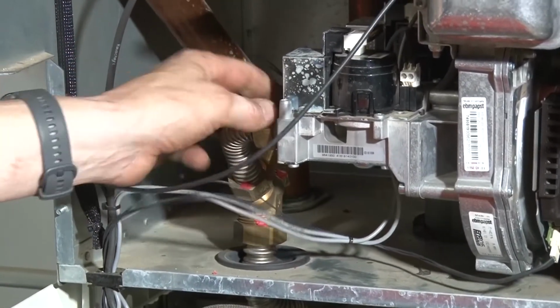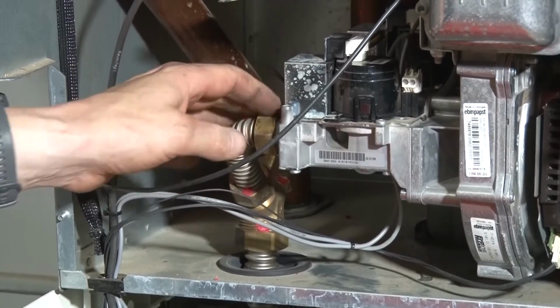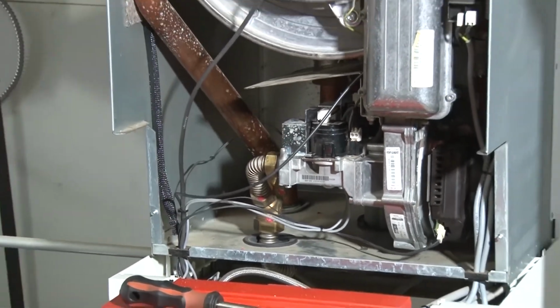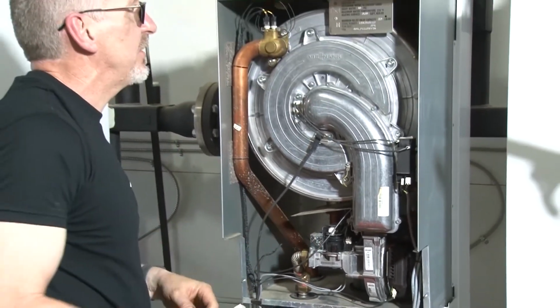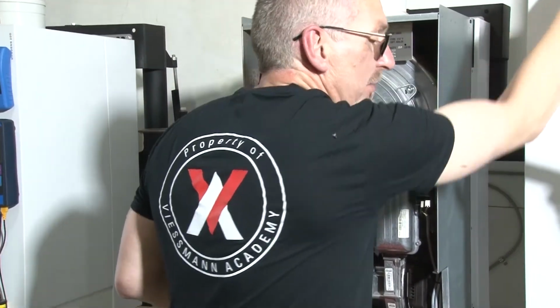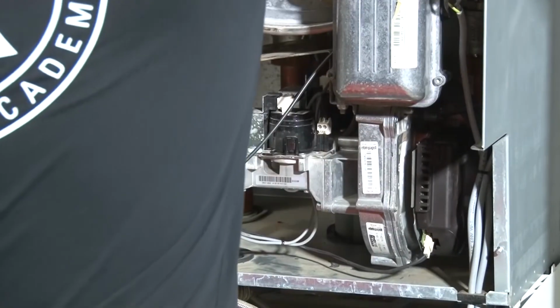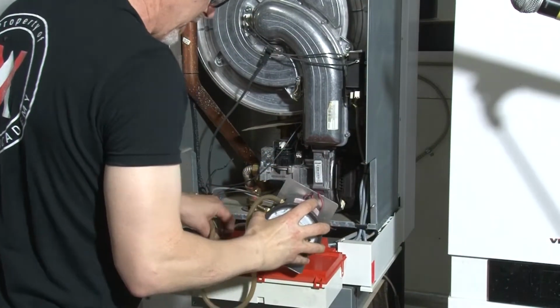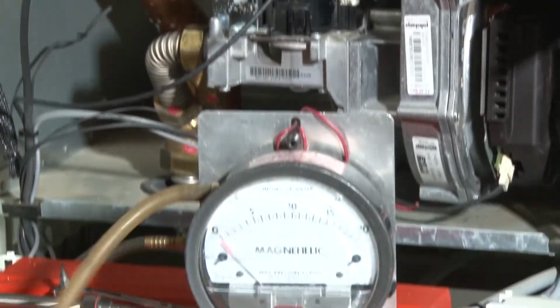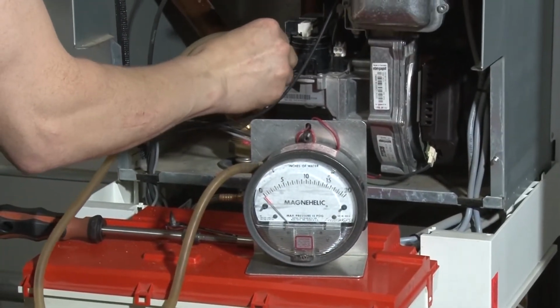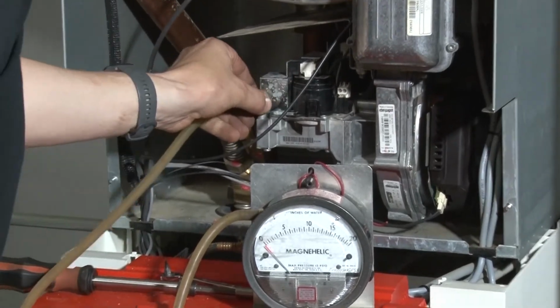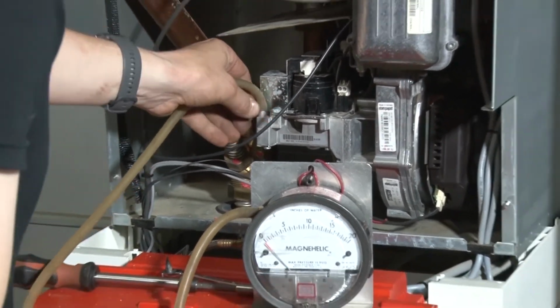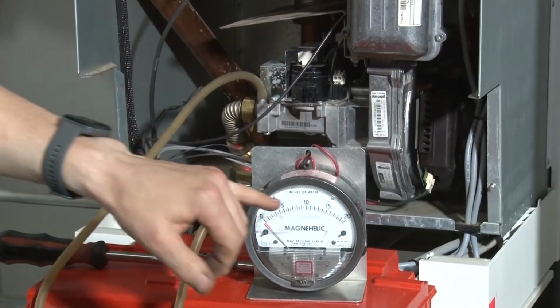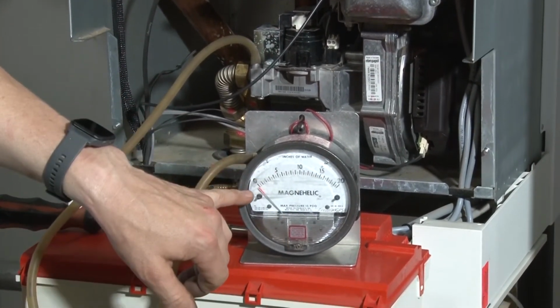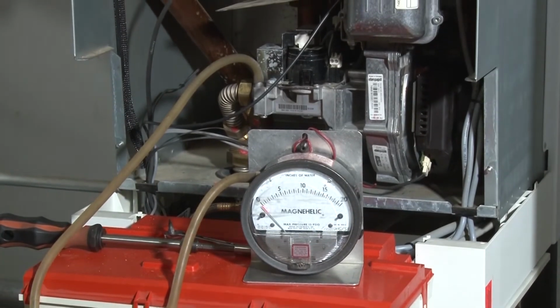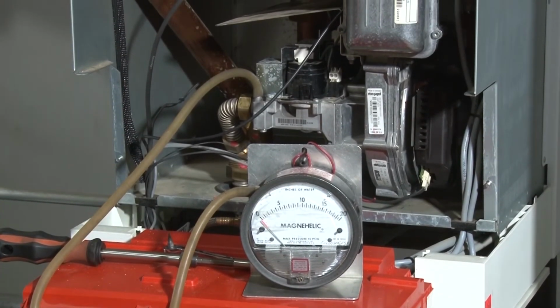So before we put the gas on here, we could soak this down and basically do a soak test on it. I'm going to put my pressure gauge on this one right now to check and measure our gas pressure. I'll put the gauge down this area here so it's a little easier to see. And what we're doing here is we're checking our static pressure. So before we fire the boiler, we want to make sure that we're not going to overfire it, and we're going to limit that to 14 inches. We don't want this gauge to go past that 14-inch mark.